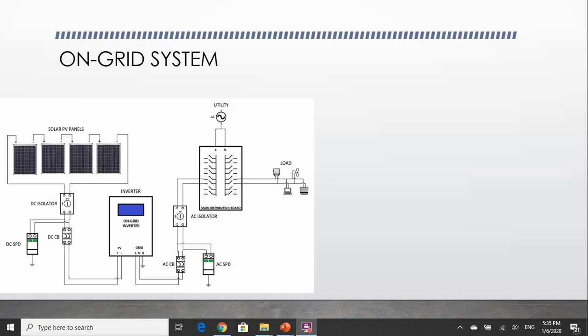Let's take a closer look at the on-grid system. The on-grid system is the simplest and the cheapest to install as it only requires two main components: the solar panels and the on-grid inverter. As mentioned, the on-grid system is still connected to the power grid — the utility. If the load power requirement is too high, it will import power from the grid. And if the solar power system generates excess power, it will export this power back to the grid and the tariff will be paid to you, assuming that you have applied for net metering.